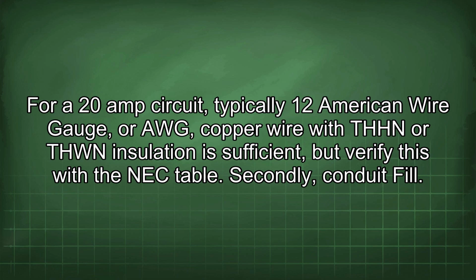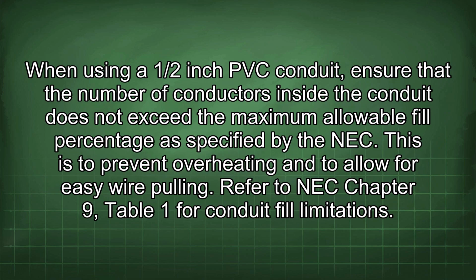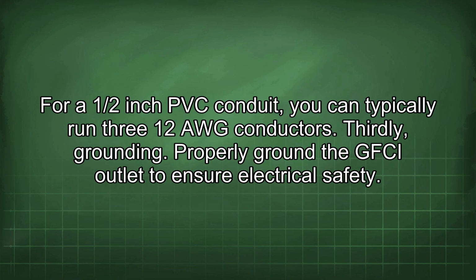Secondly, conduit fill. When using a 1/2-inch PVC conduit, ensure that the number of conductors inside the conduit does not exceed the maximum allowable fill percentage as specified by the NEC. This is to prevent overheating and to allow for easy wire pulling. Refer to NEC Chapter 9, Table 1 for conduit fill limitations. For a 1/2-inch PVC conduit, you can typically run 3 12 AWG conductors.